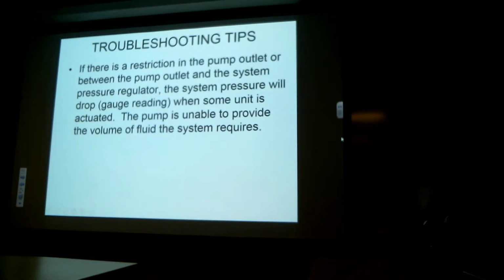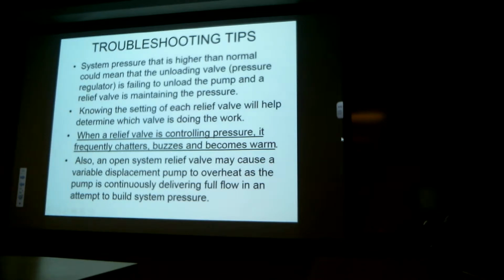Anything else? System pressure is higher than normal. You all know that in many hydraulic systems, we've got either an unloading valve or we've got a pump that contains a compensator. That's the controlling mechanism for system pressure. As a secondary device, you may also have a relief valve in the circuit as well.